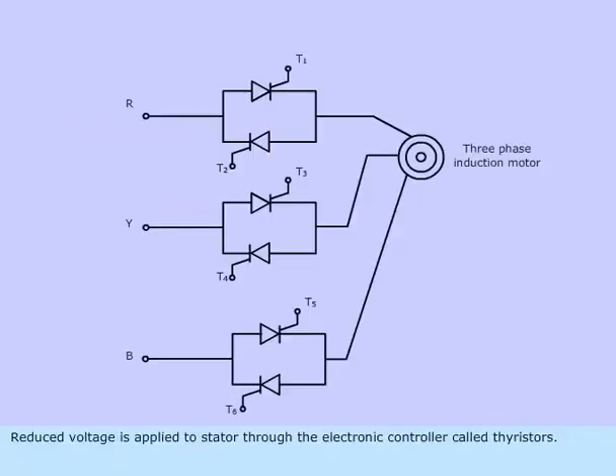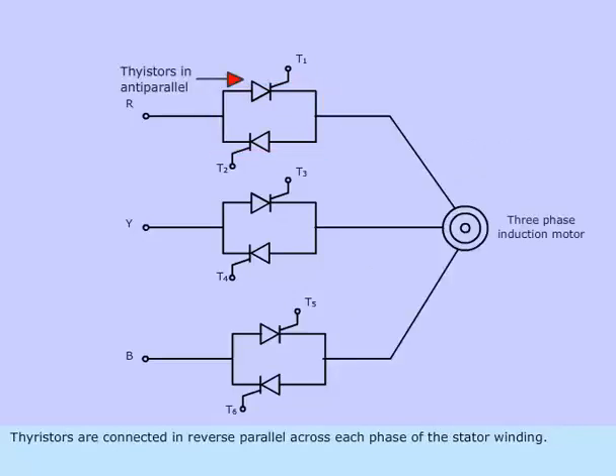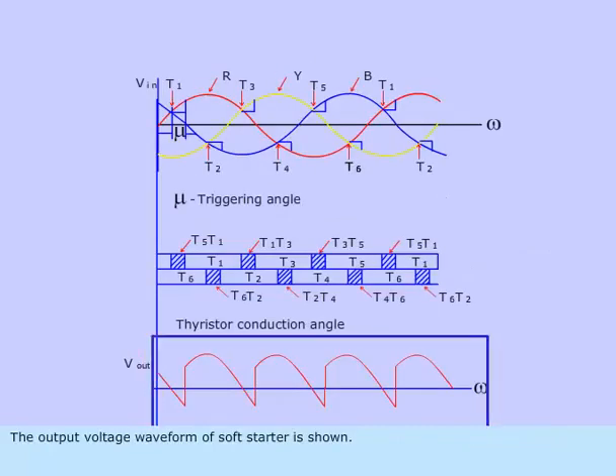Reduced voltage is applied to stator through the electronic controller called thyristors. Thyristors are connected in reverse parallel across each phase of the stator winding. The output voltage waveform of soft starter is shown.